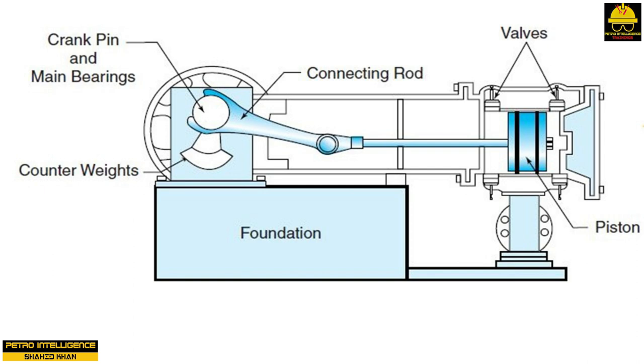Some engineering designs include pulsation dampeners to offset the problem of pulsing or spurting flow rates. The dampener should absorb cyclical flow variations. The pulsation dampener is a small pressure vessel with a diaphragm and a cushion of air to offset surges.